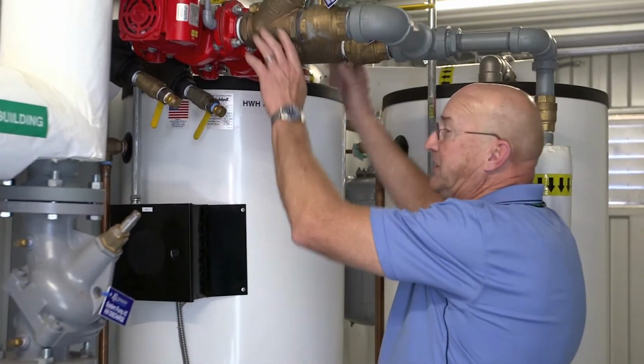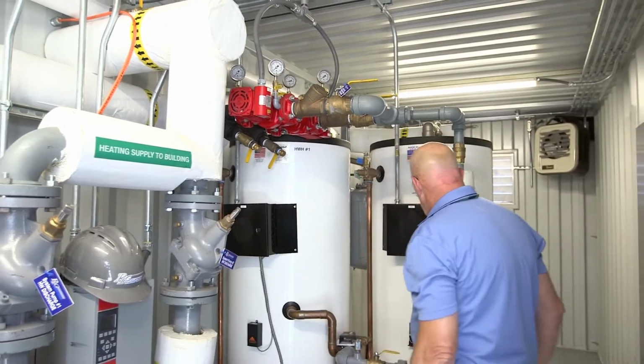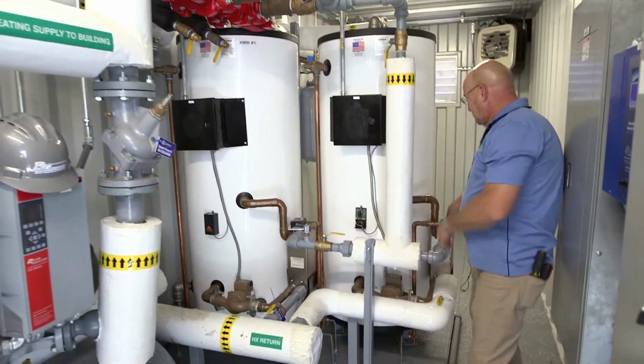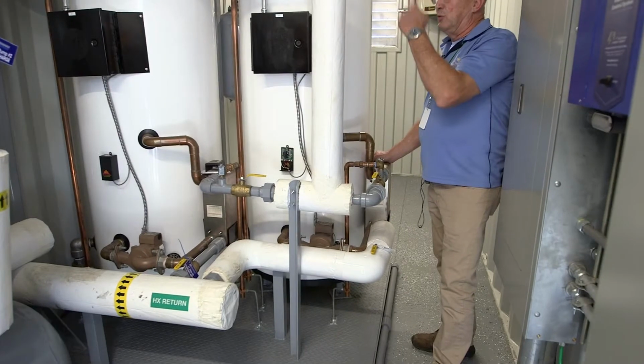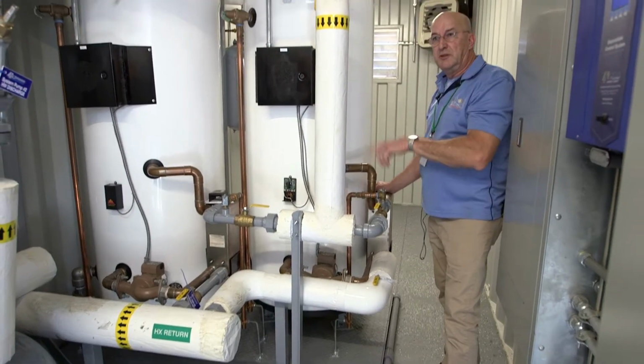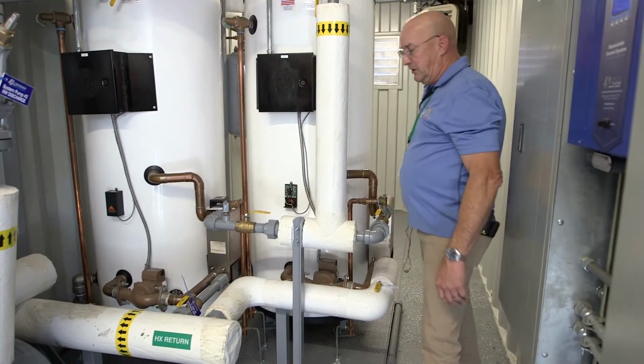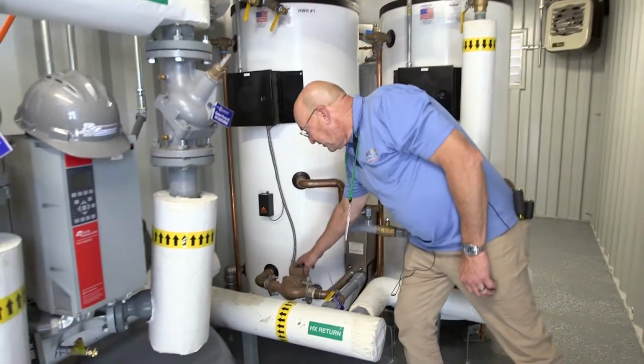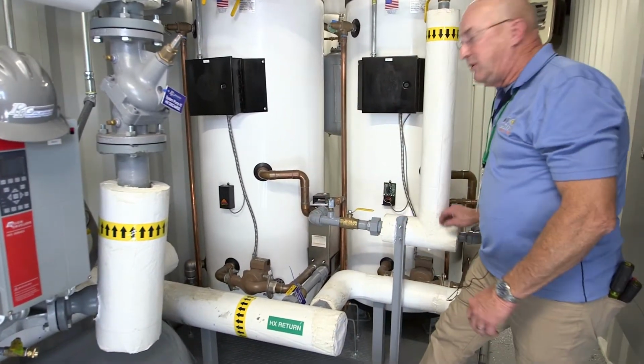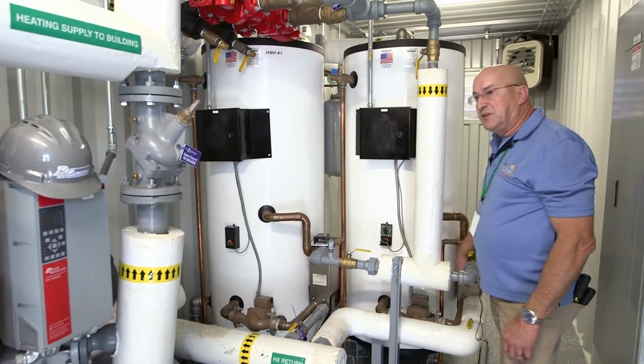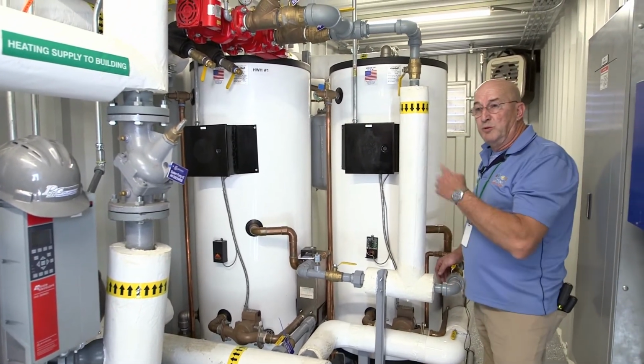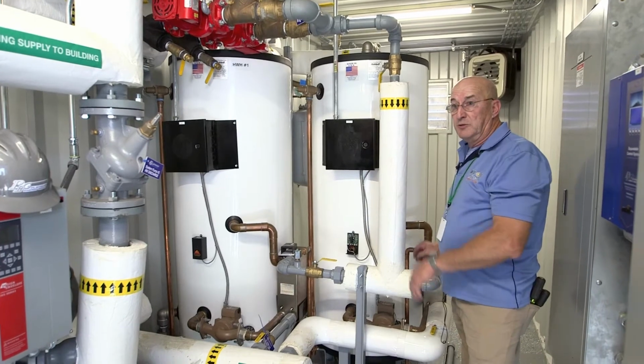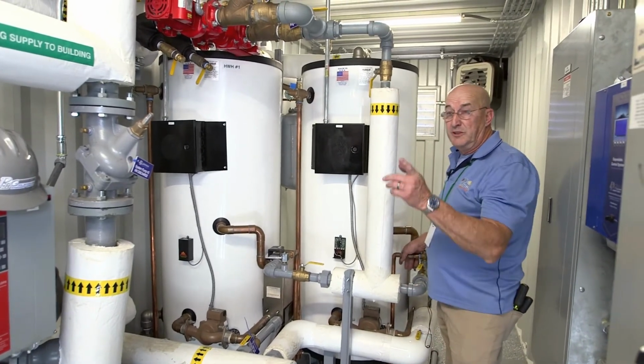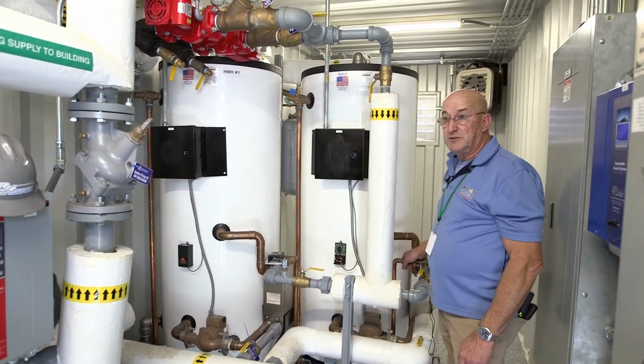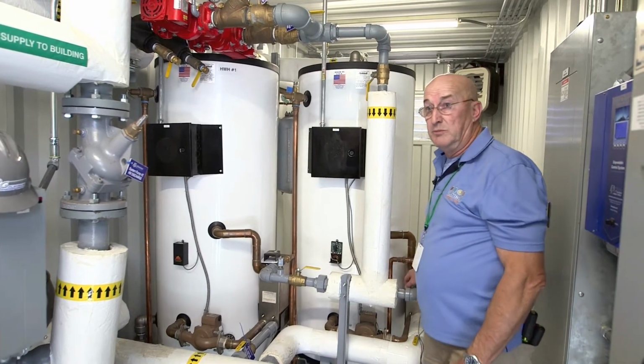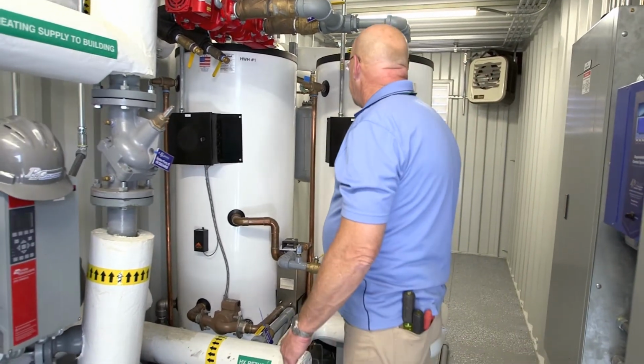These take the water from the heating system and run it through these heat exchangers. There are 2 heat exchangers. The water runs through one side of the heat exchanger to get it warm. Now you have your brass pumps down at the bottom of each tank. They feed through the other side of the heat exchanger. They move the water from the tanks through the heat exchanger, where it picks up heat from the heating system, and that's what heats up the tanks. It makes the tanks warm, and it keeps them warm.